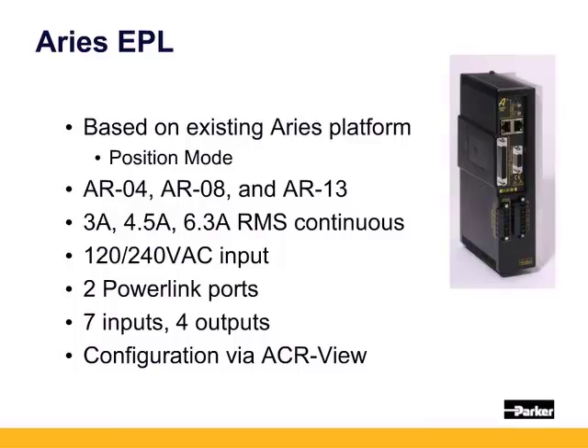The ARIES EPL drives accept 120 or 240 volts AC. They have two ethernet powerlink ports with an onboard hub, so ethernet cables can be daisy-chained from controller to drive one to drive two, etc. The ARIES EPL has a 25-pin D-sub connector with seven discrete inputs, three of which are high-speed inputs, and also four discrete outputs.